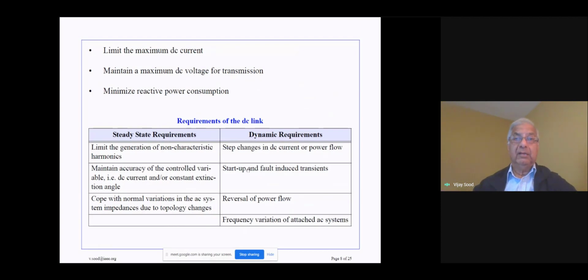On the right-hand side of this table, we have the dynamic requirements of the DC link. So the dynamic requirements are any changes in the flow of power current. We want to make sure that we can start up the system from zero. We can absorb any fault-induced transients. We also want to make sure that we can reverse the power flow in case we have a back-to-back system. Not so much in a long-distance two-terminal system, but in a back-to-back, sometimes we want to have the reversal of power flow. So we want to be able to make sure that we can do that. Finally, we want to be able to tolerate the frequency variations of the attached AC systems.